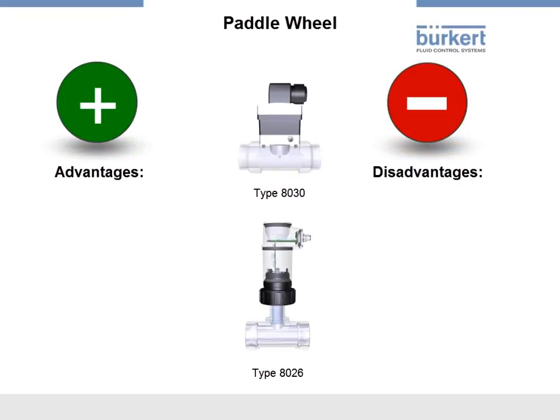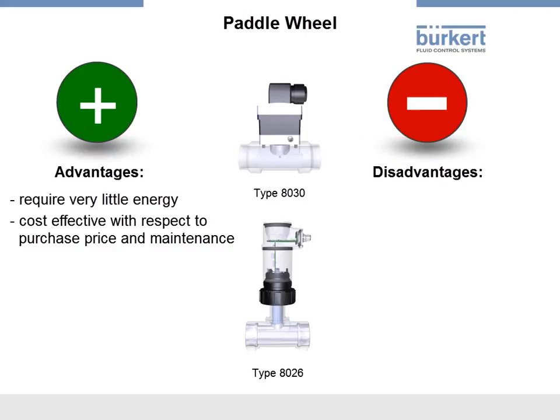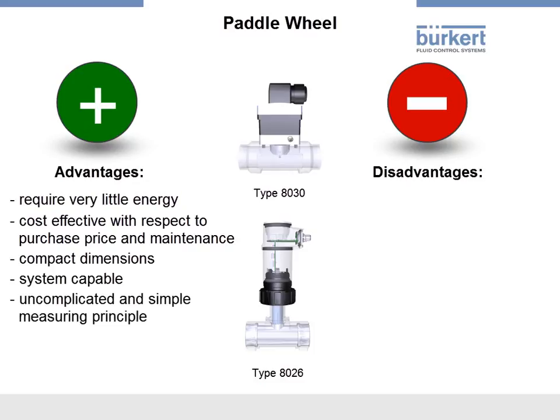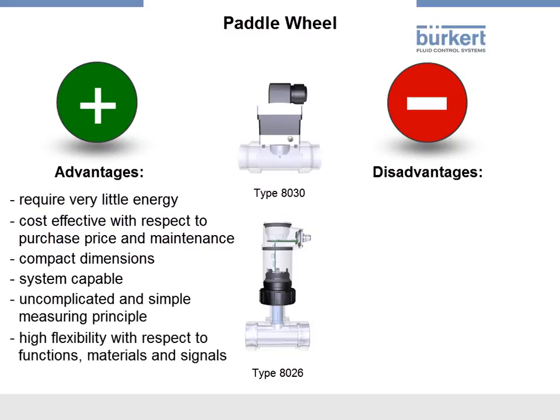To conclude our discussion of the paddle wheel, we should mention the general advantages and disadvantages of the paddle wheel measuring methods. There are many advantages to using paddle wheel sensors. They require very little energy in comparison with other measuring principles and are cost-effective with respect to purchase price and maintenance. The compact dimensions and the modular design make the inline units system capable. Another plus is the uncomplicated and simple measuring principle, which results in high flexibility with respect to functions, materials, and signals. An advantage that should not be overlooked is that the measurement is not dependent on conductivity.